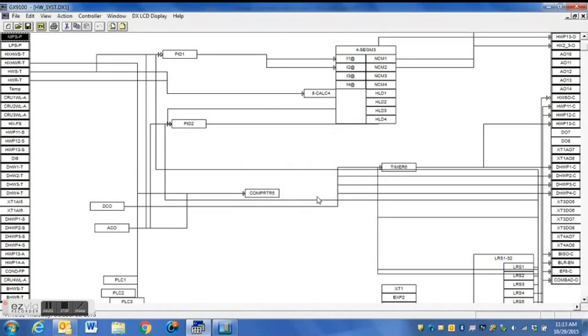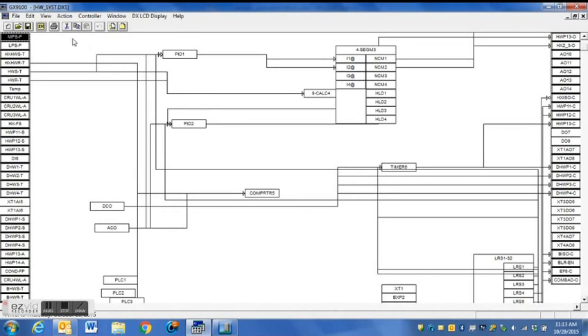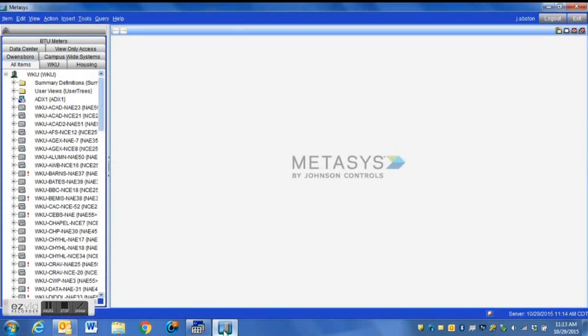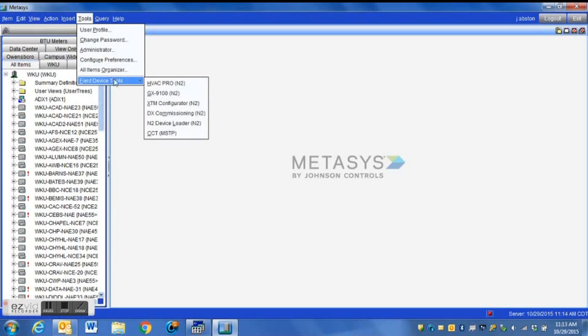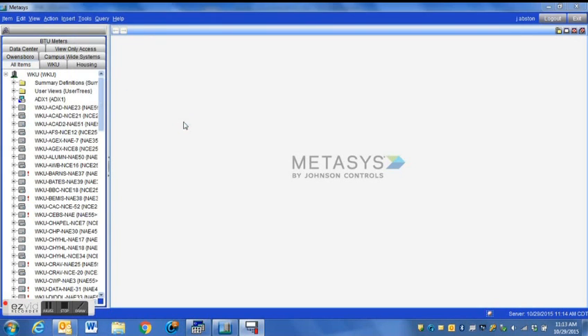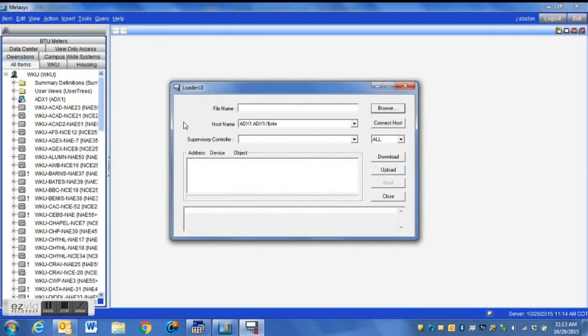Once that is done, you will then open up your Metasys Extended Architecture, and that is where we're going to be using the N2 device loader. Now you need to make sure that you have your pass-through tools installed onto your computer. Then we open Metasys Extended Architecture, go to tools, and open the N2 device loader.